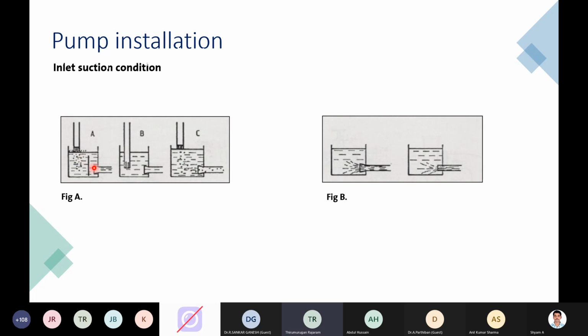The same thing when you're taking a suction: air entrapment will reduce the pump performance. Some kind of baffle arrangement will help you avoid water turbulence getting into your pump inlet pipes. Slightly enlarged pipe openings on your suction will reduce your velocities, and you get smooth entries rather than a flat opening, so a conical entry should be used. Even if you buy an 85% efficiency pump, if you do not take care of all these things, your pump will not operate as an efficient pump.